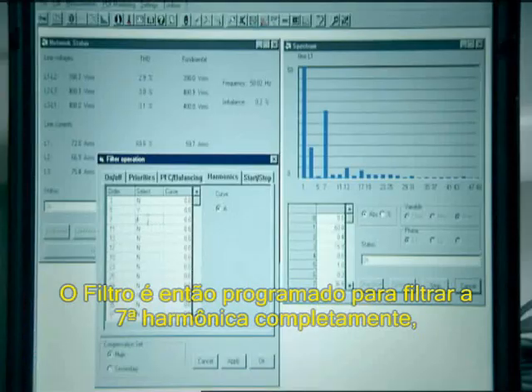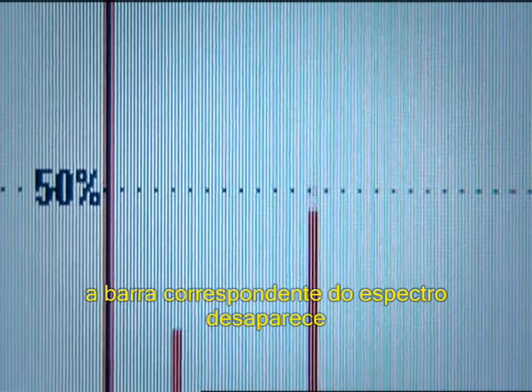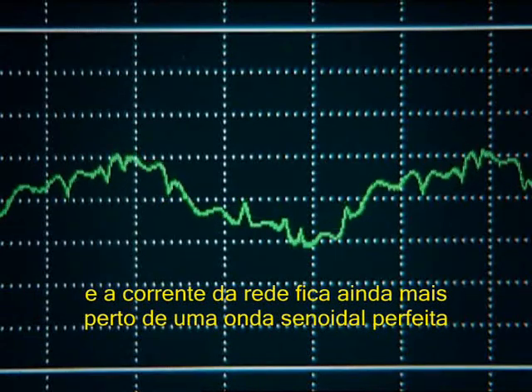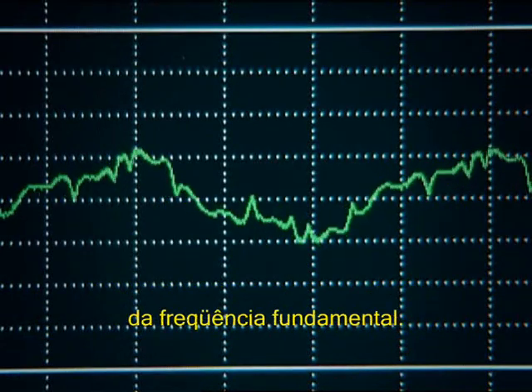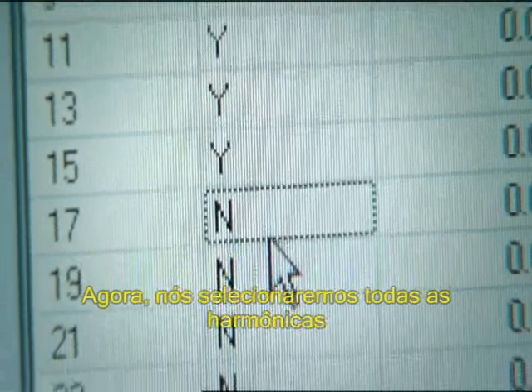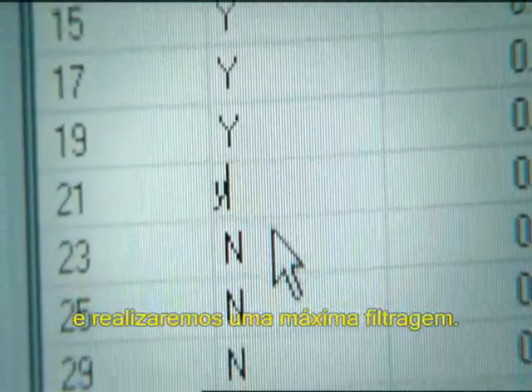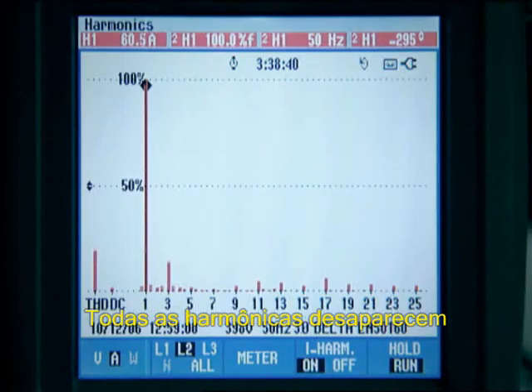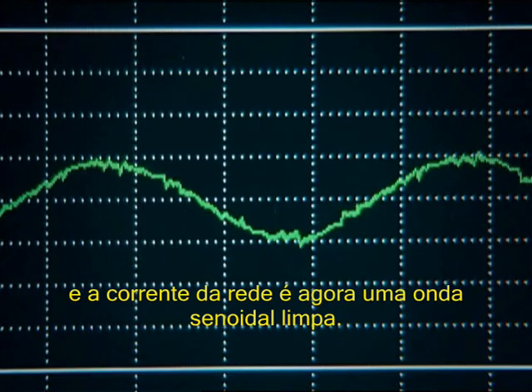The filter is then programmed to filter the 7th harmonic completely. The corresponding bar of the spectrum disappears, and the line current is even closer to a perfect sine wave at the fundamental frequency. We shall now select all the harmonics and perform maximum filtering. All the harmonics disappear, and the line current is now a clean sine wave.